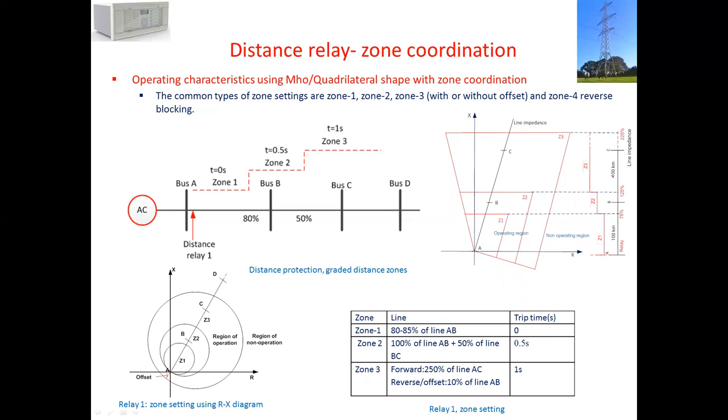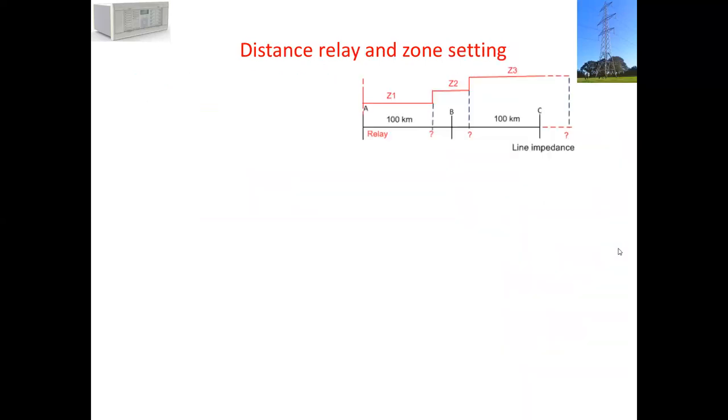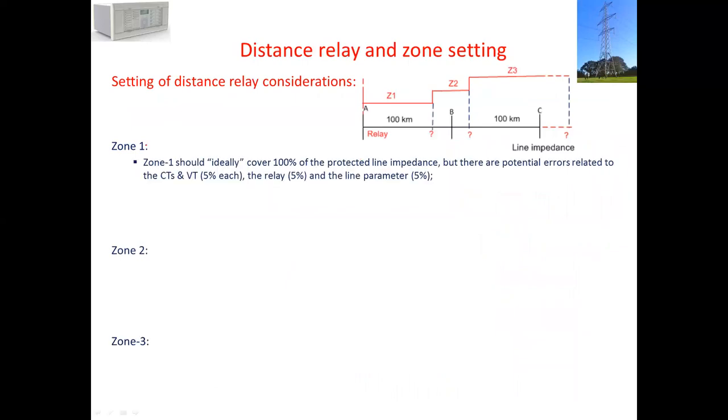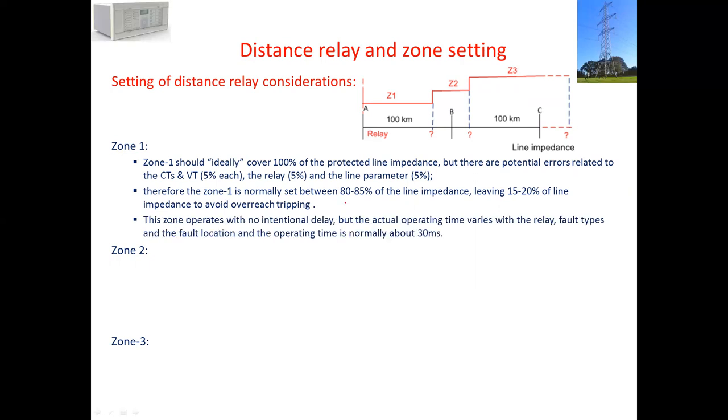The question is, how do we consider zone 1 at what percent, zone 2 at what percent, and zone 3? One of the reasons is that zone 1 should ideally cover 100% of line A to B. But because we have errors caused by CT, VT, relay, or line parameters, all added up to 20%, we can set zone 1 up to 80% to 85% of the line impedance. For modern relays, we can set up to 85% because they are more accurate. The operating time is 0 second, but actually it is around 30 milliseconds because of relaying time.